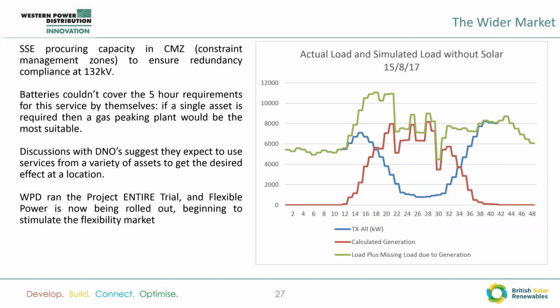Looking at these two use cases in the wider market, things are beginning to happen. SSE is looking to meet its N-2 obligations at 132 kV using constraint management zones, offering energy storage or gas or diesel peaking plants. The batteries couldn't do the 5-hour requirements for this service economically by themselves, but they do have the fast response that then could be the front end to other longer term generation. And some DNOs expect to have many contracts with different assets to get the desired result out of the system. And WPD is also beginning Flexible Power to try and stimulate the flexibility market, speaking to people who have assets already.